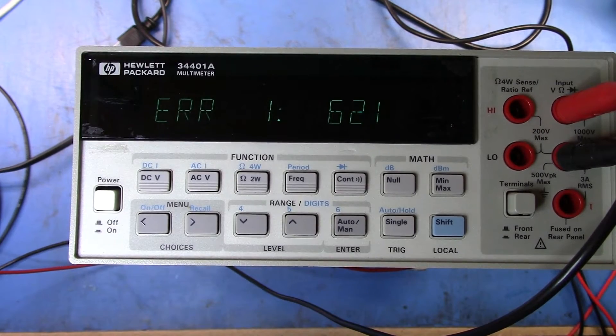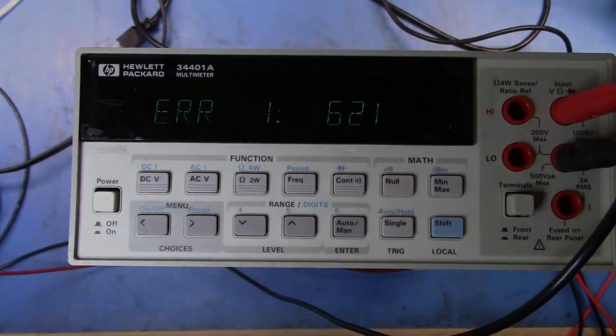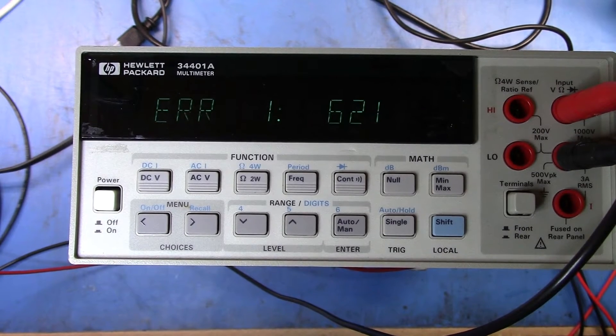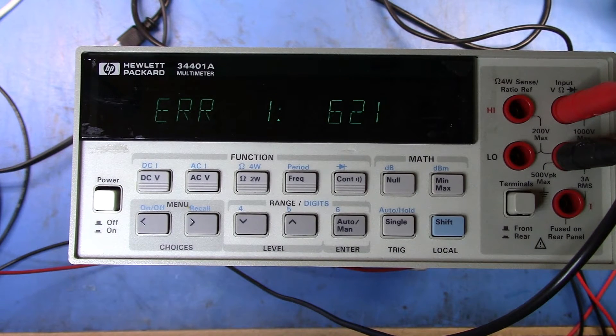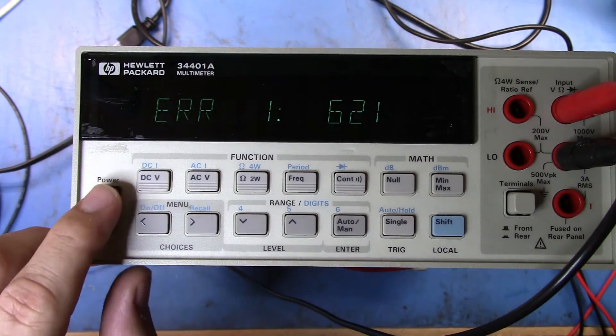Let's go take a quick look at the service guide and see what that error is. A quick look at the service manual tells me that 621 is an AC RMS full scale fail. And a quick little Google around tells me that it is a simple error, most likely caused by CR305. So, let's pull the unit apart and take a quick look at that.